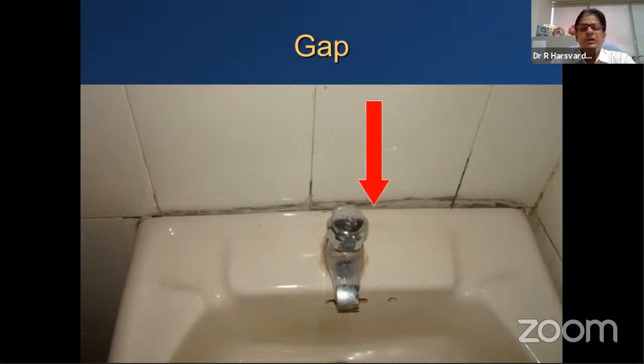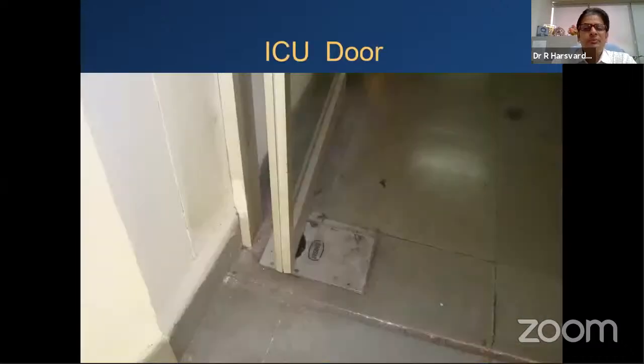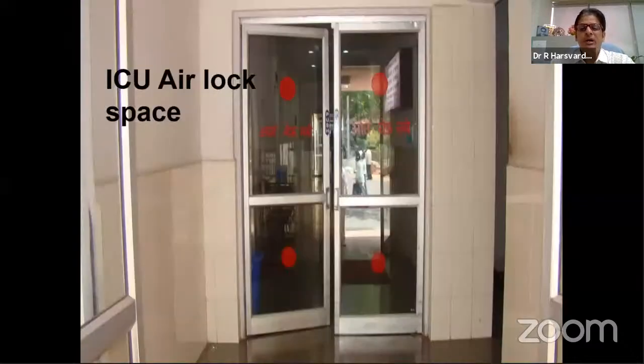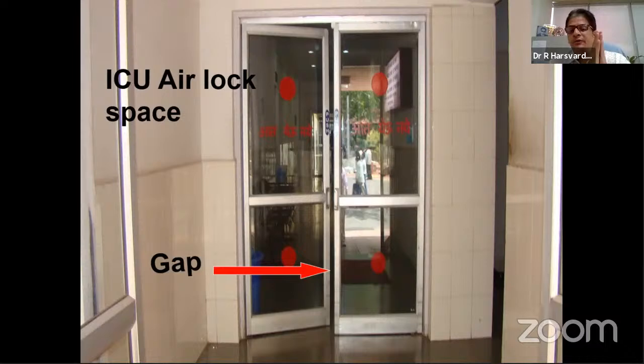As regards ICU, there should be adequate space around the bed to access both the patient and the equipment. Individual cubicle for each patient to reduce transmission of infection in the unit. Alcohol-based hand rubs should be located within 2 meters of the point of care, and there should be separate designated sinks for cleaning the equipment. The airlock and air curtains should be there at the entrance, and air change should be 15 air changes per hour. And one ought to have an isolation facility of two isolation rooms per cubicle of 8 beds, that is for HAI.